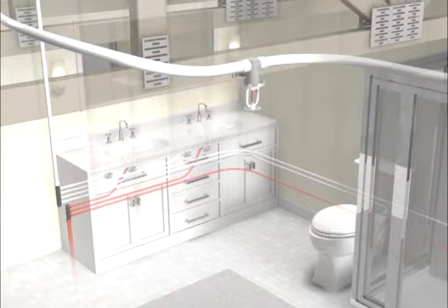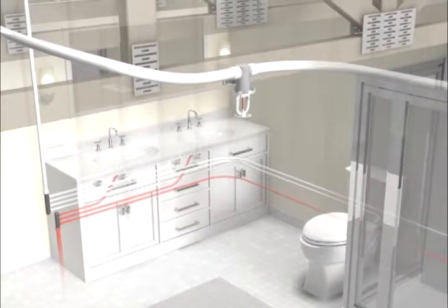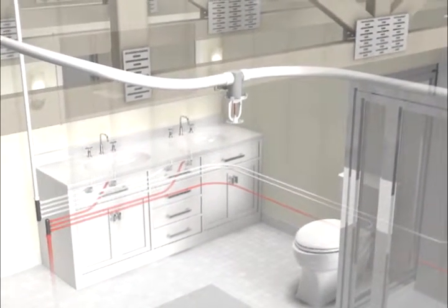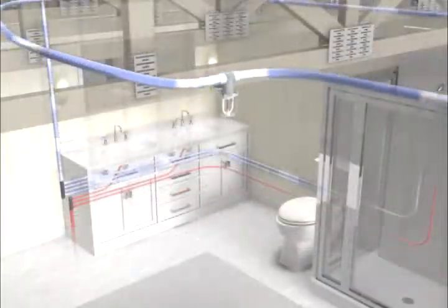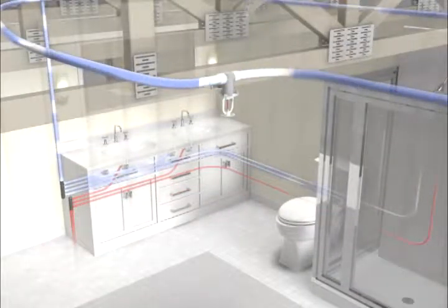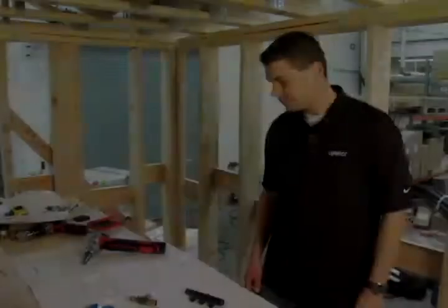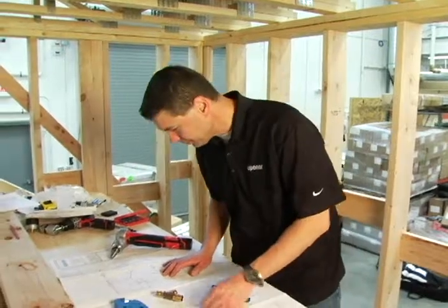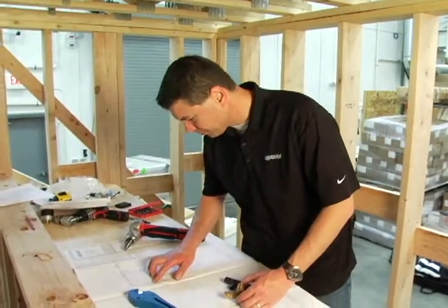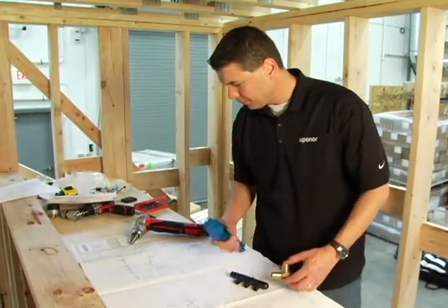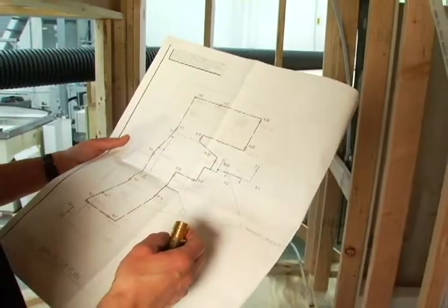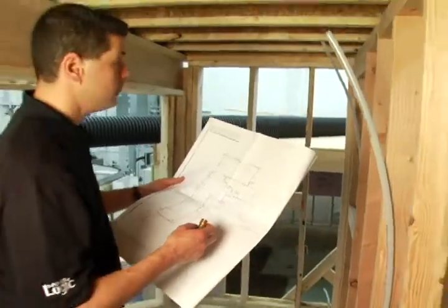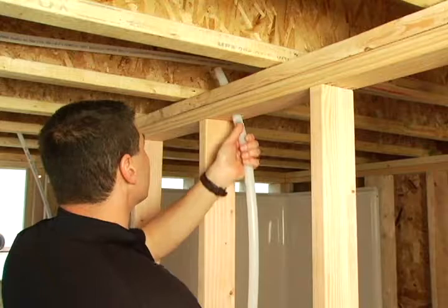Uponor's AquaSAFE system is a multi-purpose system, which means it's integrated with the home's cold water plumbing. This simple layout eliminates the need for expensive backflow preventers and check valves and the annual inspections and maintenance that they require. To connect the sprinkler system with the cold water plumbing, simply cut brass tees into the sprinkler lines near the fixture groups. Locate your plumbing connection points, which will be identified on Uponor's sprinkler design layout.